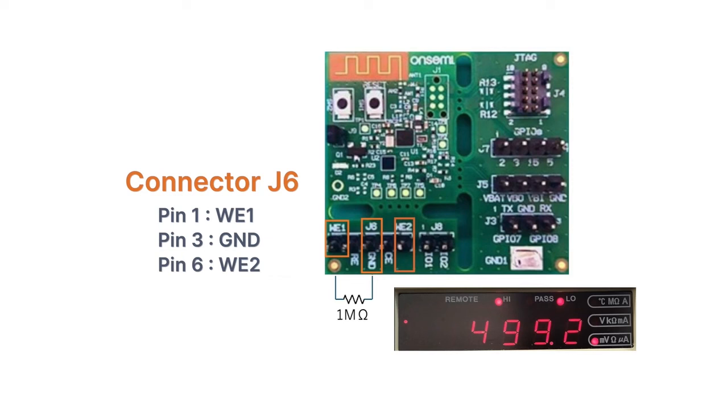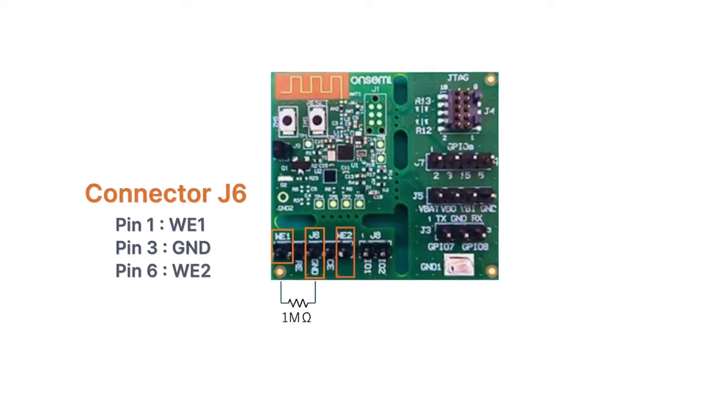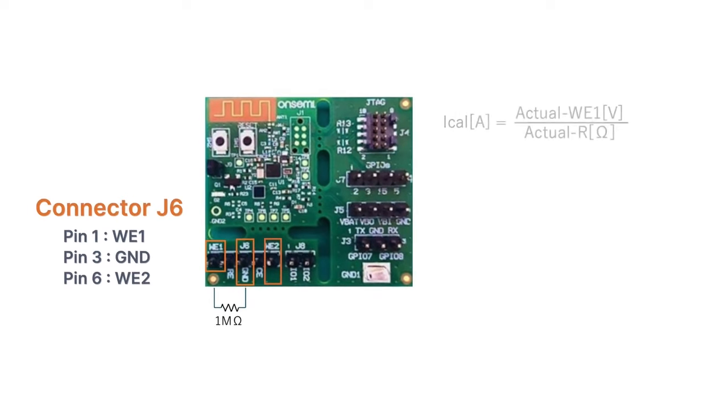Measure with WE1, either in an open state or with a sufficiently high resistance such as 10 megaohm between WE1 and ground. Label this value as actual WE1 volts. Next, measure the accurate resistance value of the resistor to be inserted between WE1 and ground. Label this as actual R, ohm.